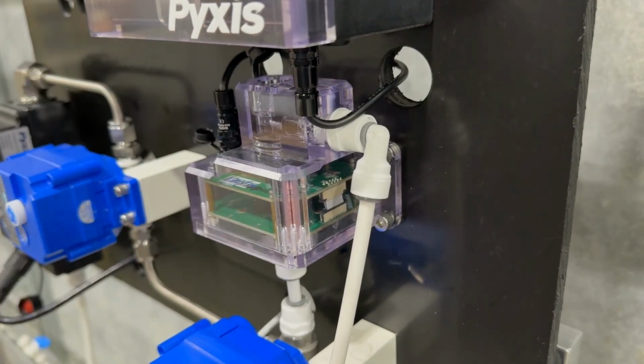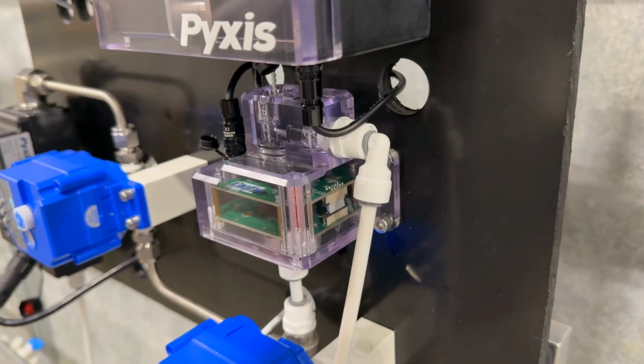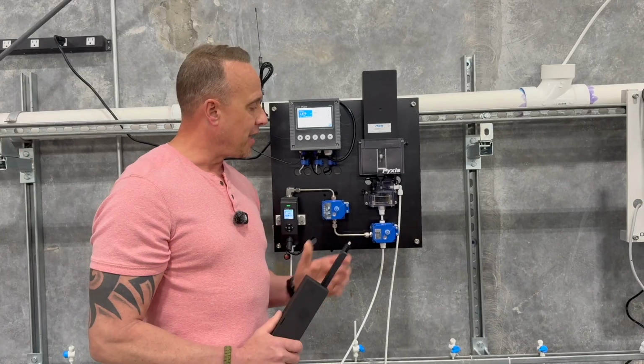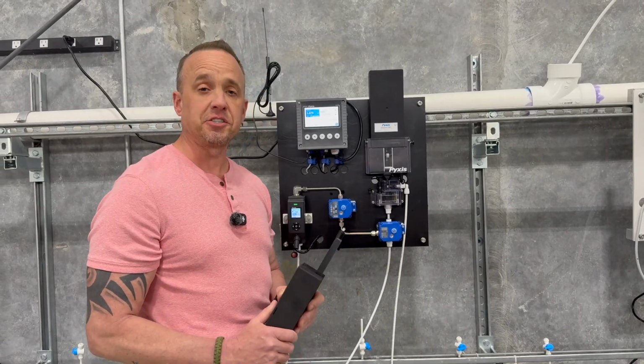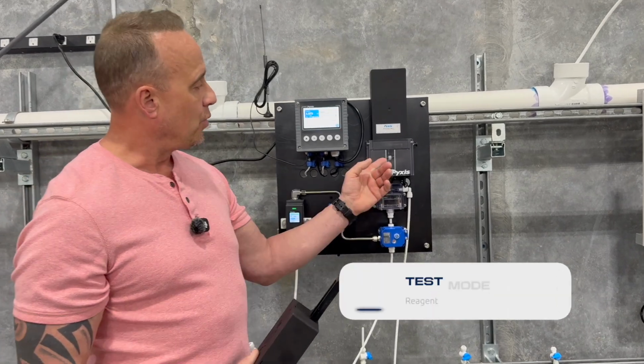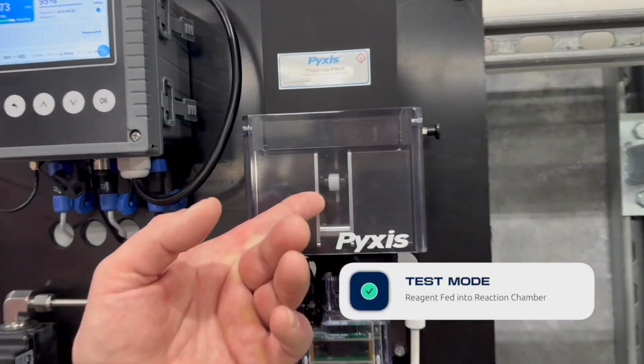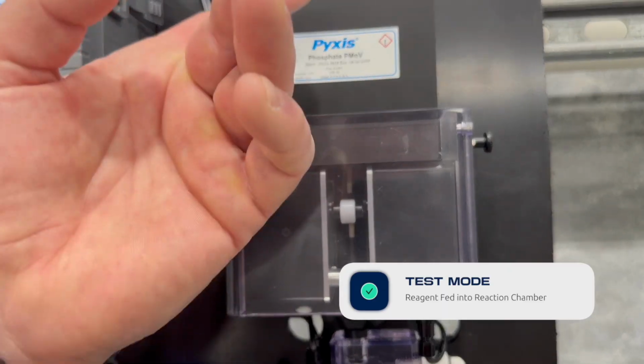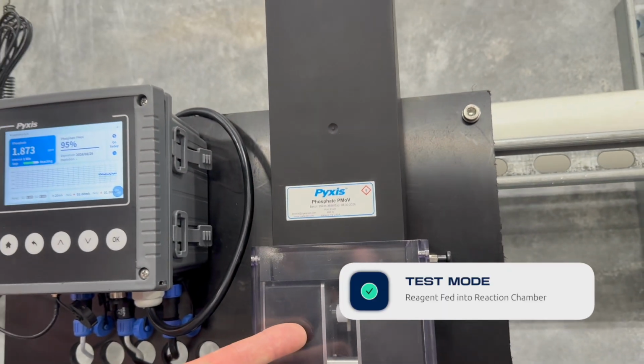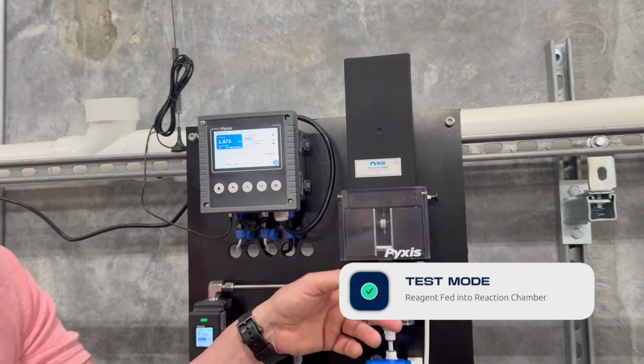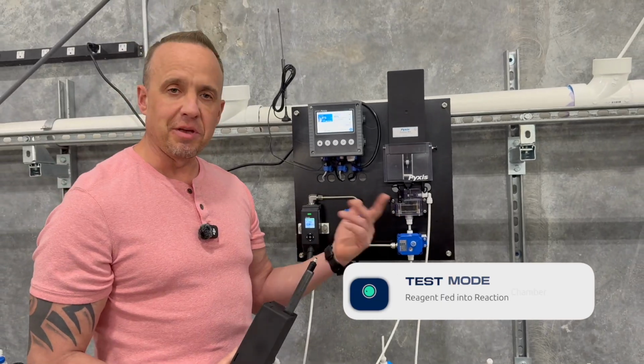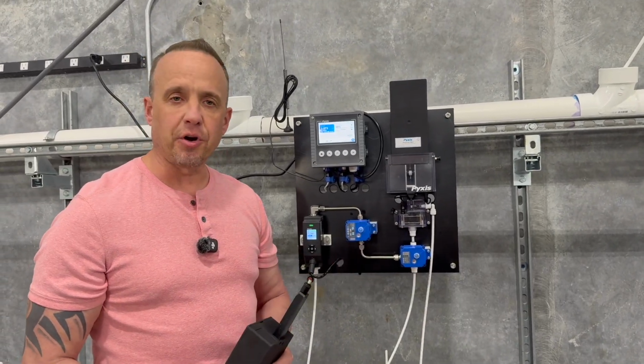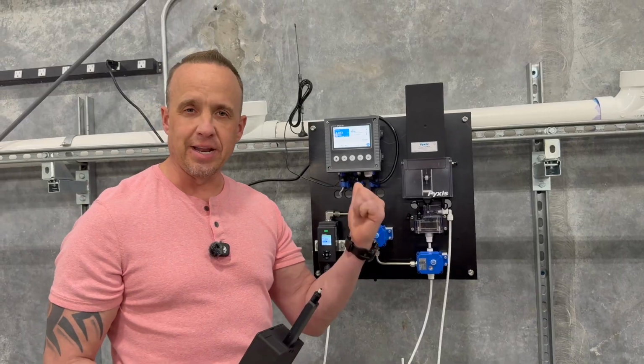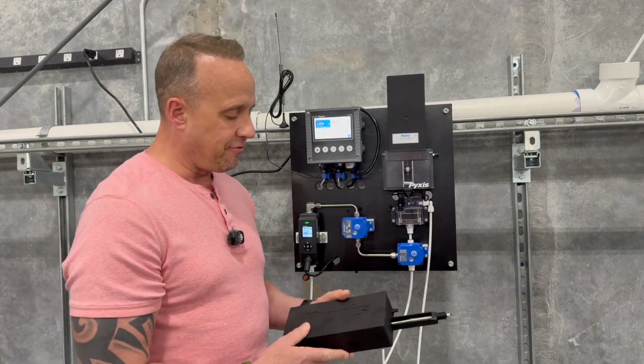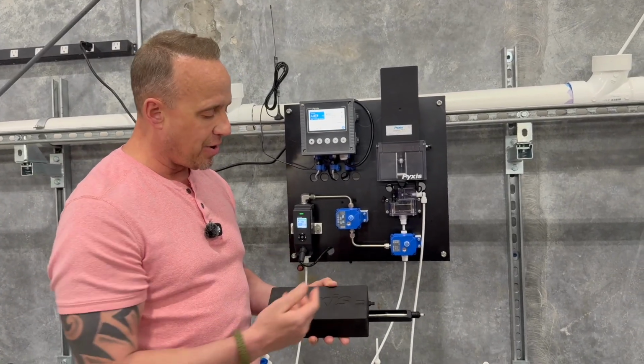Inside of the reaction chamber is a magnetic stir with a Hall effect flow sensor to monitor the stirring rate of the reaction chamber, and that's when the unit goes into actually test mode. During the test mode process, we actually have a small cam-driven rotating actuator here, which will then take reagent from the disposable reagent cartridge and administer it into the reaction chamber. During that process, the mixer is mixing, and then the reaction timer occurs, and after the reaction timer is done, the reading is taken.